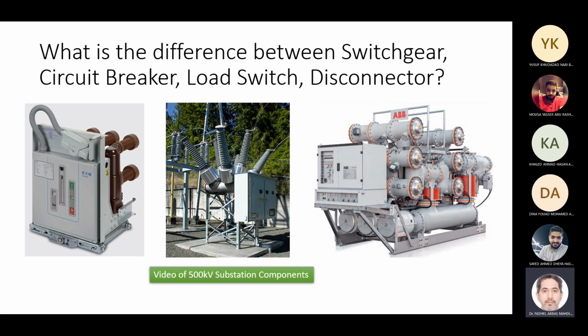If you look at these pictures, do you know what the difference is between a switchgear, a circuit breaker, a load switch, and a disconnector, Shabab? Switchgear can be switched manually, but the circuit breaker can depend on the fault and relay command, right? Maybe what you mean is a switch. The switch in general, a load switch, can be motorized. Generally, it's manually operated, but can be a motorized switch.